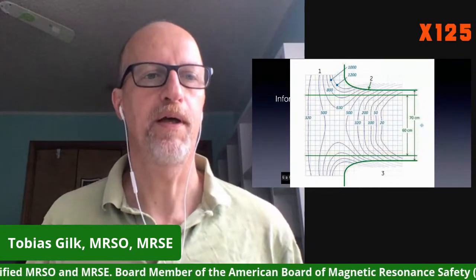This diagram is showing ISO gradient values. This chart on the right-hand side is the center of your MRI scanner, and those curved lines represent the mouth of the bore. In almost all MR systems, these spatial gradient values are radially symmetric, which means we could be looking at a coronal view, or a sagittal view of the mouth of the bore, and it would be equally true in any orientation, looking at the mouth of the bore.